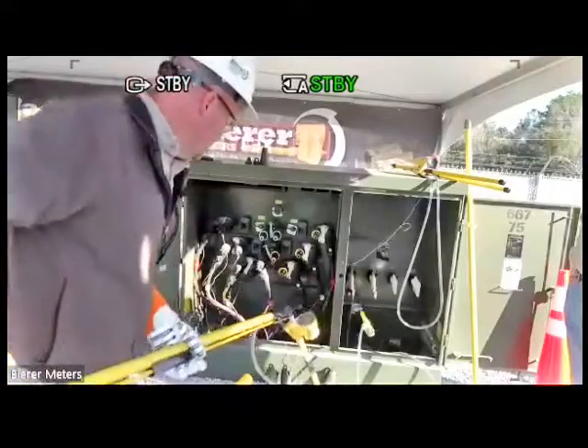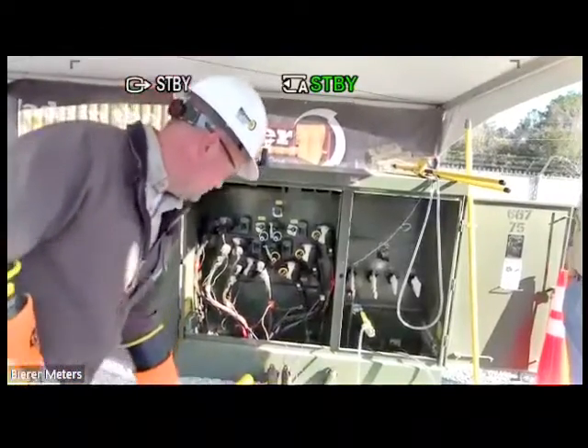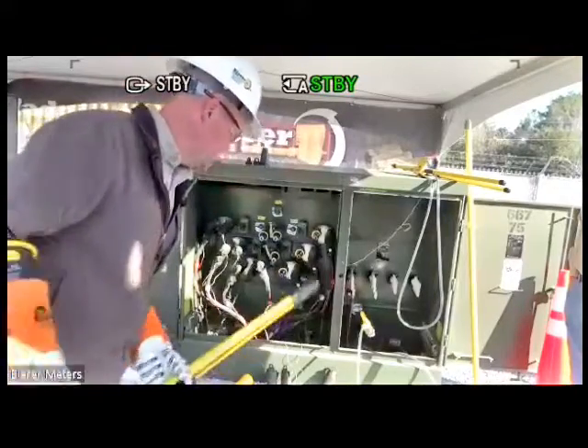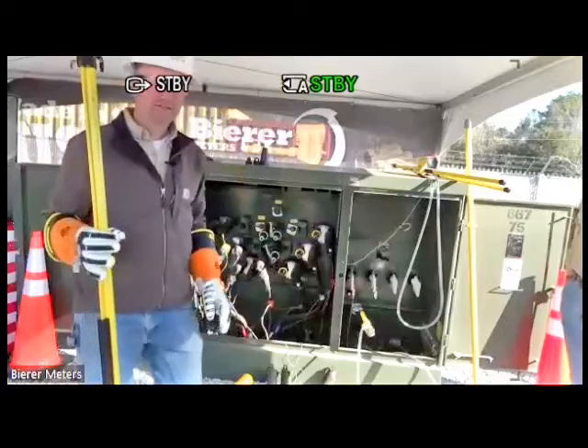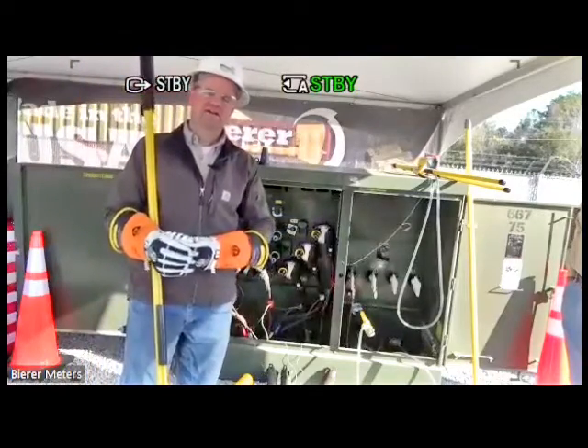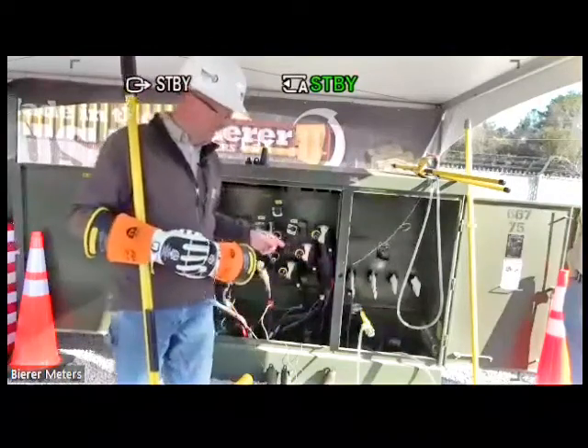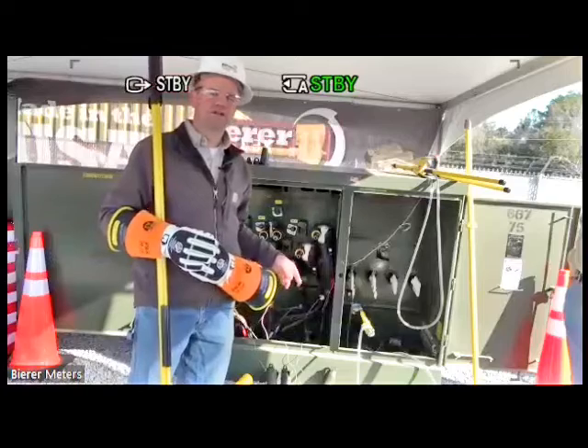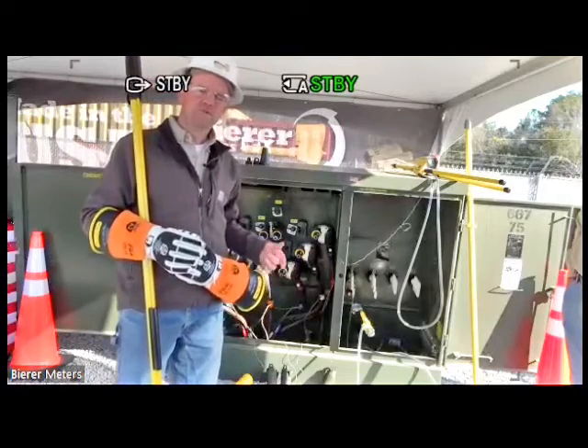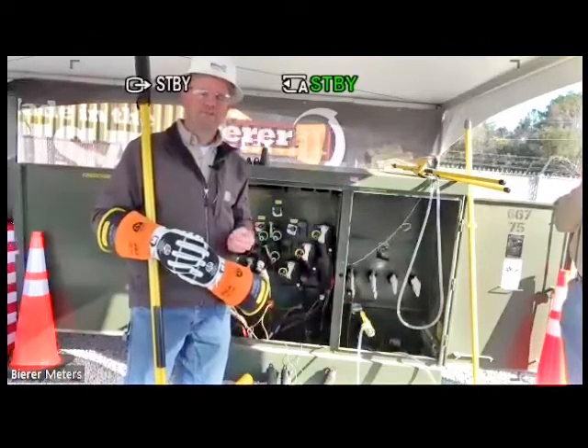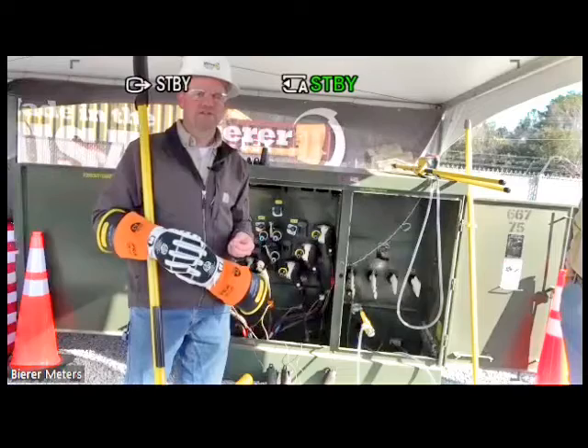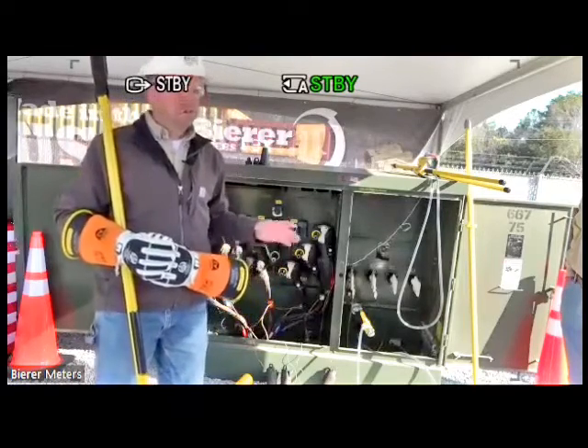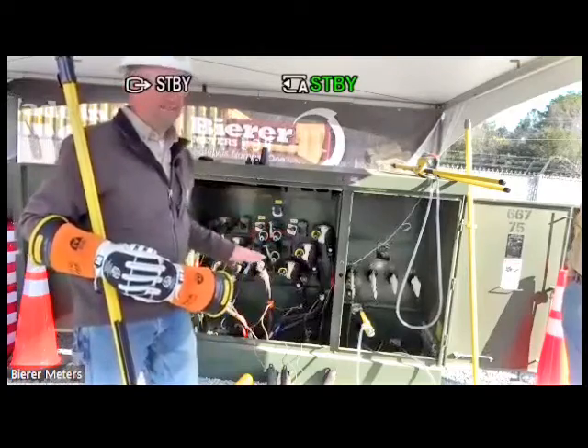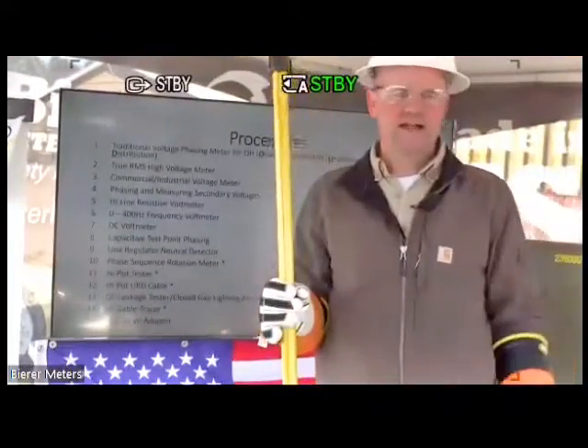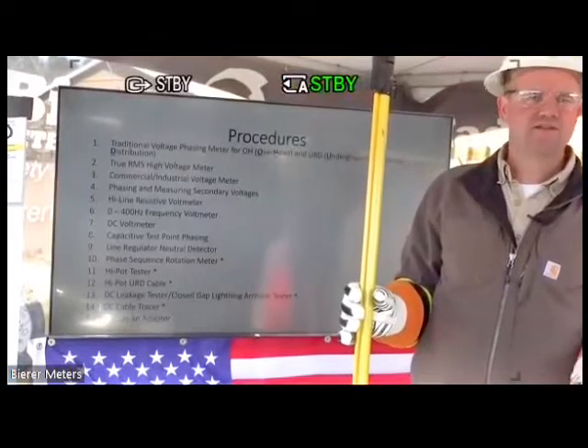Again, the PD50 will operate exactly the same. No difference whatsoever, with the exception of the scale. What I mean by that is since the PD50 is a higher rated device, instead of having 25 million ohms per probe, it has 50 million ohms per probe. So instead of seeing 50 volts for every microamp of leakage, you see 100 volts for every microamp of leakage. Okay, so that is the only difference that you'll notice. But as far as the operation of the tool, it operates exactly the same as what we just did here. High pot tester is exactly what we just did, testing the high pot adapter itself. That's a high pot tester. Again, that's a single use tool.